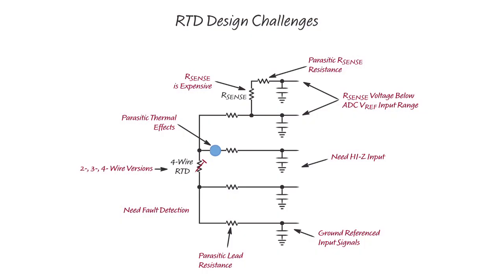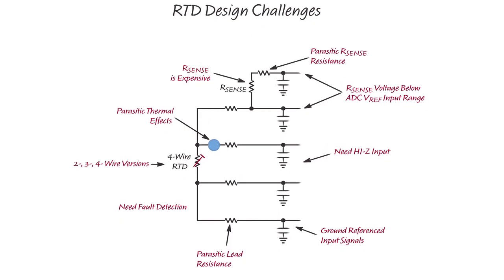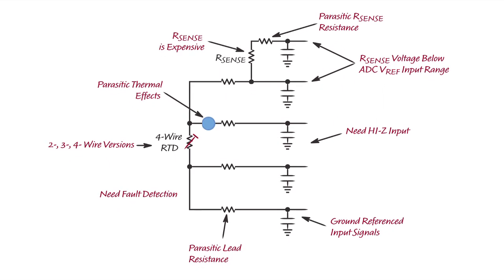An RTD's resistance variation with temperature can be very small. For example, a PT100 RTD varies approximately 0.03 ohms per tenth of a degree C. Measurement accuracy can be compromised by external input protection and filter circuits, lead resistance, and parasitic thermocouple effects.